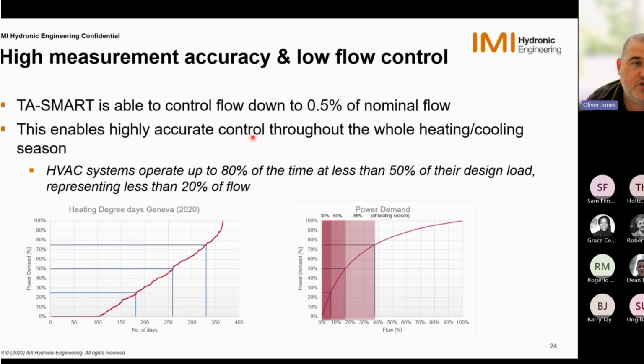So the smart valve is able to control flow down to 0.5% of its nominal flow. So the amount of flow that's permitted through that valve. So this means we can come down to a very small amount and gives us a highly accurate control throughout the heating and cooling season. What you can see from these graphs is typically for 80% of the heating season, we're actually only going to be delivering 50% of the design load, which only represents 20% of the flow. So we still have this full range of flow available for the last 20% of the year.